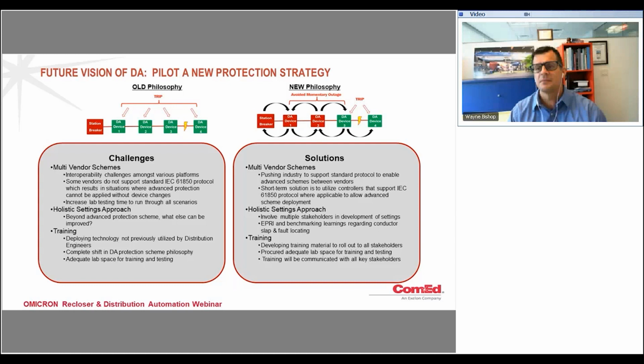For example, if a fault occurs between device 3 and 4, the circuit breakers in device 1, 2, and 3 will detect a fault current and signal to their neighbors. Since device 3 did not see a signal from device 4, it did not shift to slow tripping and opened, and then device 4 opened on loss of voltage to isolate the fault, so saving momentaries to everyone upstream of device 3.